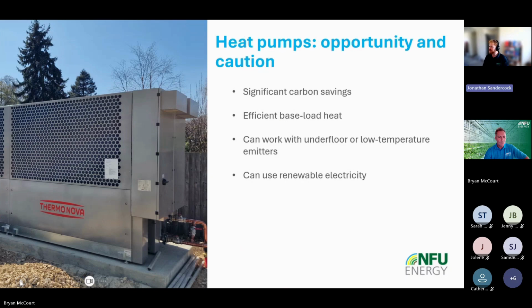I just wanted to touch on this because it links back to something that Josh was bringing up on grid connectivity capacity and how that is getting quite punitive at the moment if you're increasing your demand. So many poultry farms are either already operating or considering operating on water-based heating infrastructure. So some people may be considering heat pump technology. They are a low carbon source of heat, which is fantastic if you have sustainability goals and aspirations that you want to meet. However, it moves a large part of the heating demand onto the electricity supply compared to traditional systems.